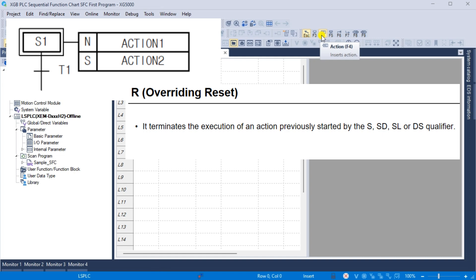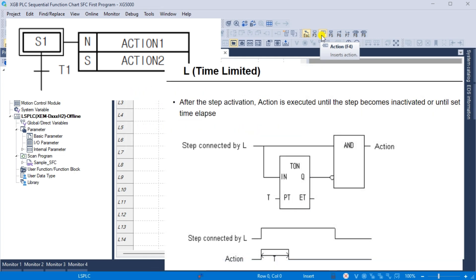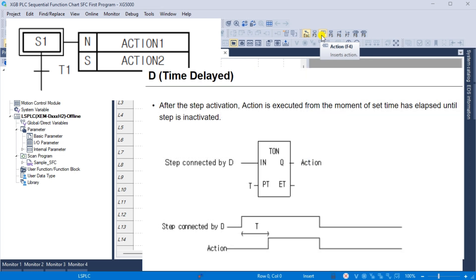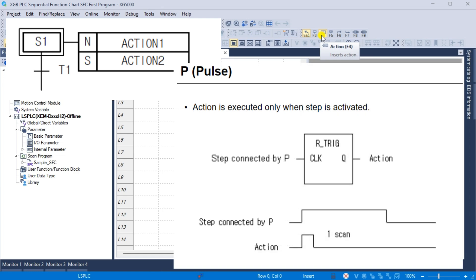R, overriding reset: it terminates executing an action previously started by the S, SD, SL, or DS qualifier. L, time limited: after the step activation, action is executed until the step becomes inactive or until the set time elapses. D, time delay: after the step activation, action is executed from the moment the set time elapsed until the step is inactivated. P, pulse: action is executed only for one scan when the step is activated.